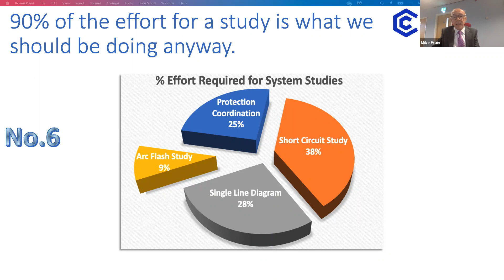Again, in my guidebook, I describe in the chapter on myths and mistakes a fault level study, protection coordination study, and an arc flash study that I carried out for a large teaching hospital about 10 years ago. I uncovered a design flaw where there are two MVA voltage optimization units. So this is heavy duty equipment here. They were installed into a critical care block, between each transformer and the main low voltage 400 volt switchboard.